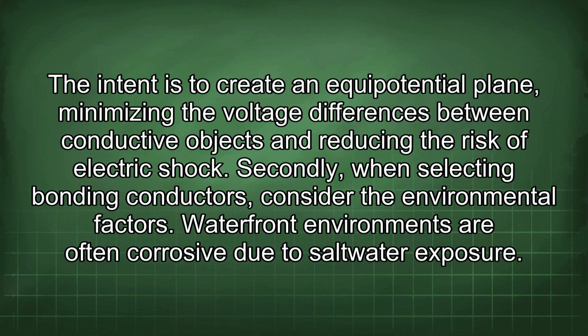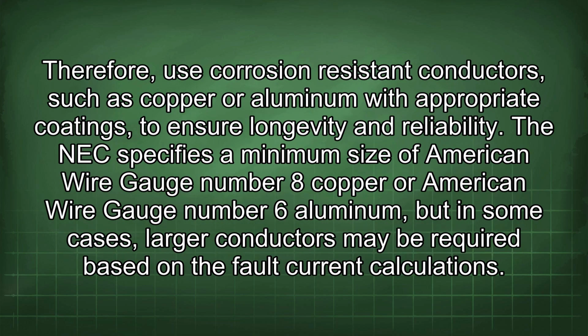Secondly, when selecting bonding conductors, consider the environmental factors. Waterfront environments are often corrosive due to saltwater exposure. Therefore, use corrosion-resistant conductors such as copper or aluminum with appropriate coatings to ensure longevity and reliability. The NEC specifies a minimum size of American wire gauge number 8 copper or American wire gauge number 6 aluminum, but in some cases, larger conductors may be required based on the fault current calculations.